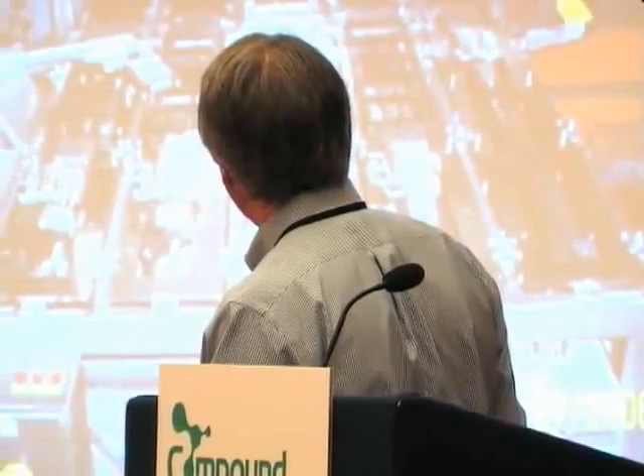So this is a picture of the picking head, the picking station. It's got 5 tray handlers here, and an upper picking head right here, and there's a lower one that looks very similar to it underneath. So pins come up from the bottom, drive the tubes out of the rack into this upper head, then it moves over to the destination, and pins there drive them down. The plates enter way over here on the side.